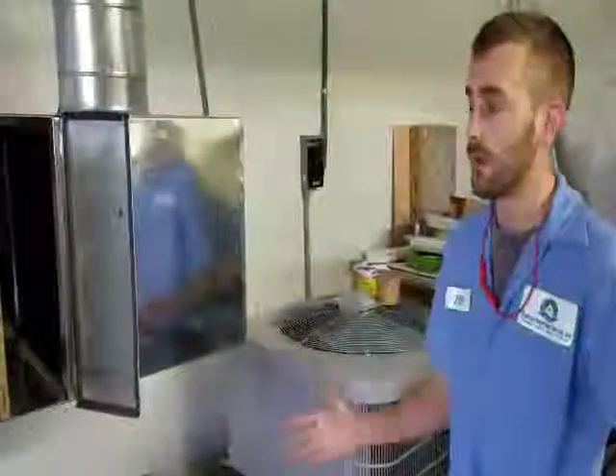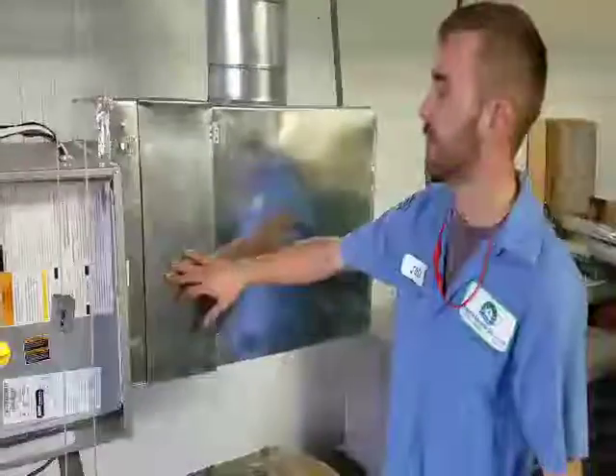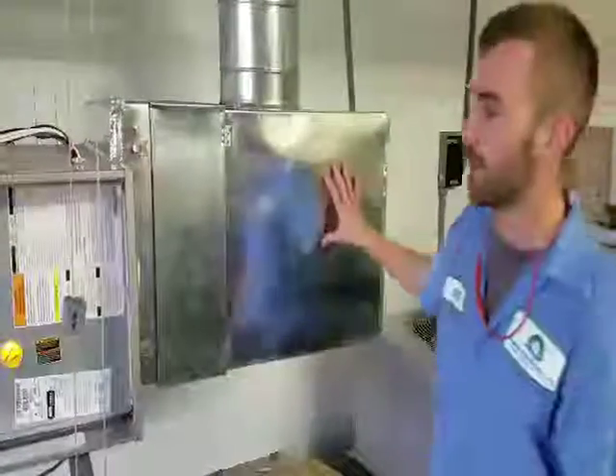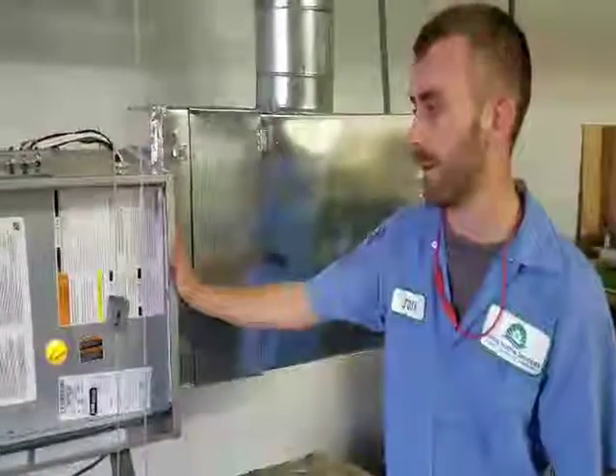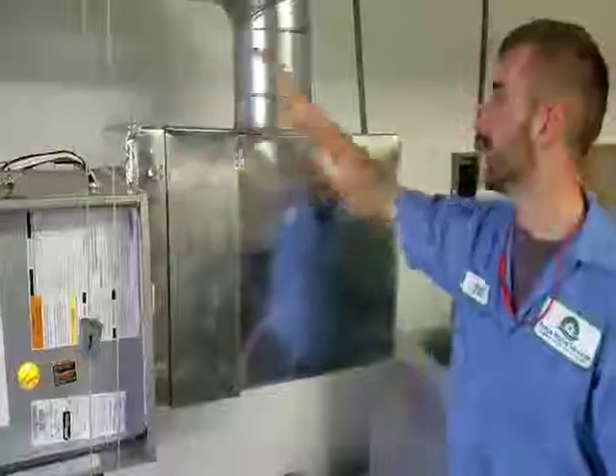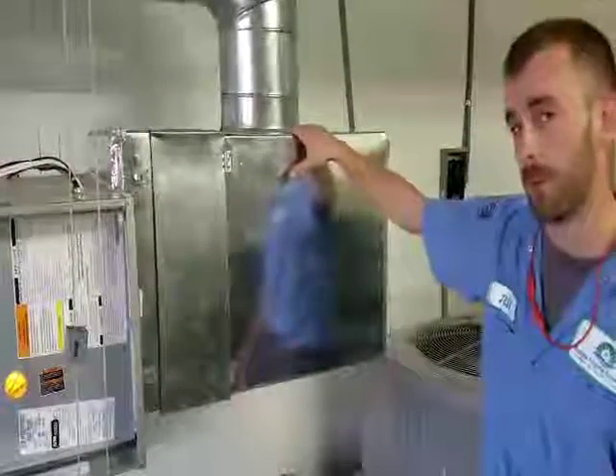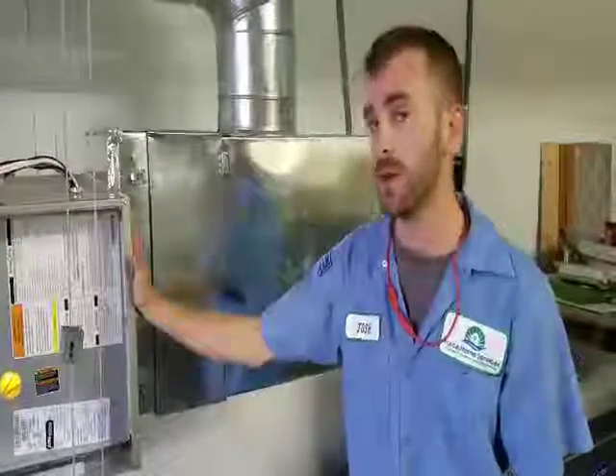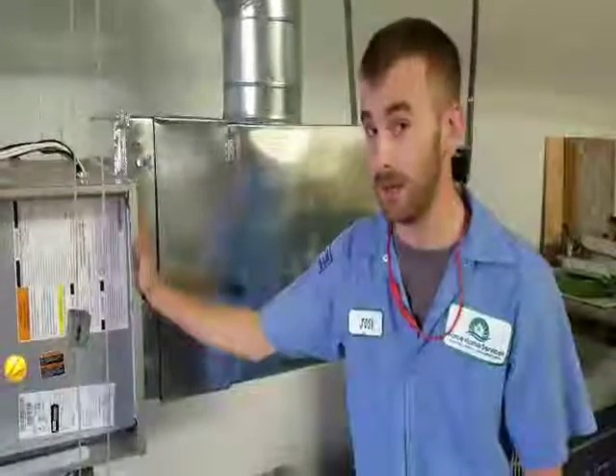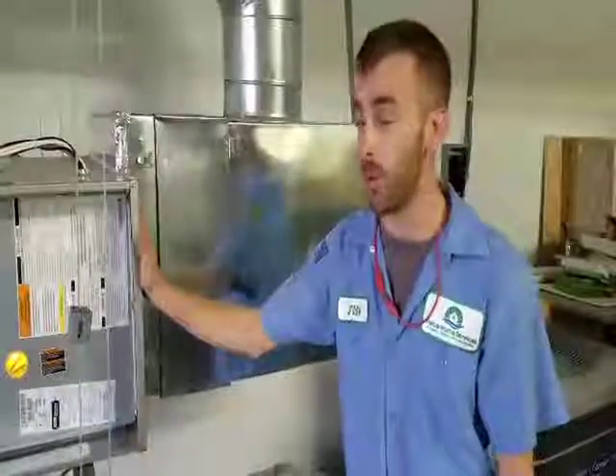Another thing I want to go over is this return plenum. Return plenums are typically attached to the end of the furnace. Now, if you have just the ductwork and no return plenum attached to your furnace, you have a guaranteed crack in your heat exchanger, and that has to do with poor airflow.